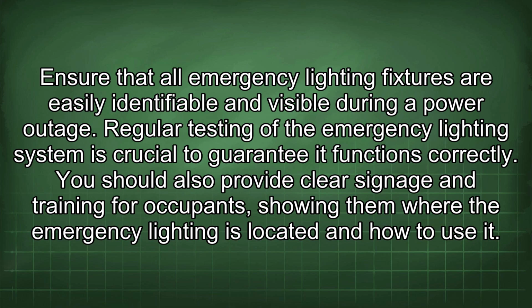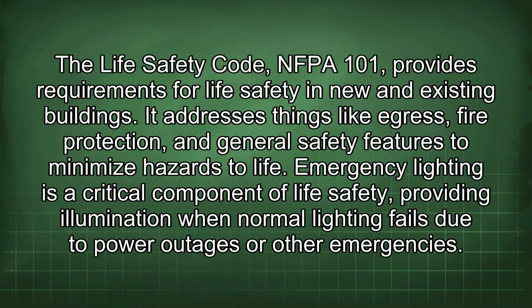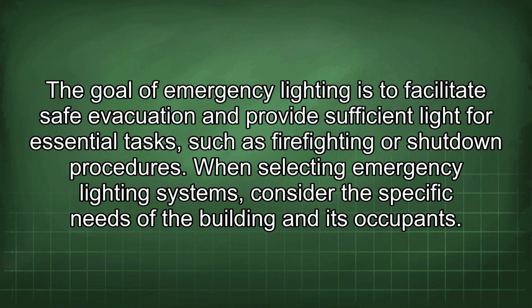The Life Safety Code, the NFPA 101, provides requirements for life safety in new and existing buildings. It addresses things like egress, fire protection, and general safety features to minimize hazards to life. Emergency lighting is a critical component of life safety, providing illumination when normal lighting fails due to power outages or other emergencies. The goal of emergency lighting is to facilitate safe evacuation and provide sufficient light for essential tasks such as firefighting or shutdown procedures.